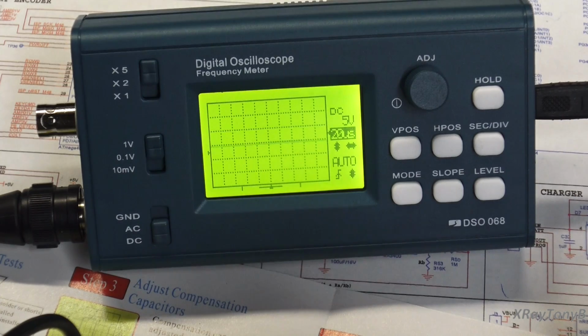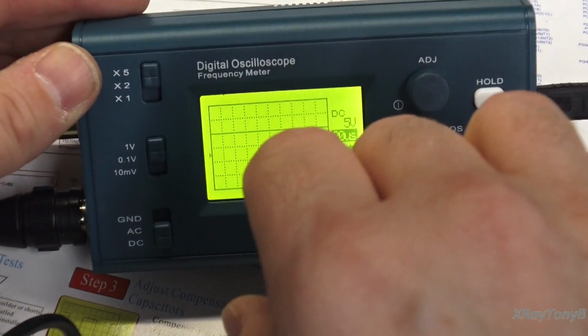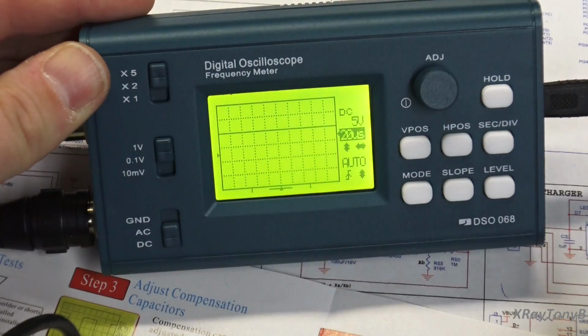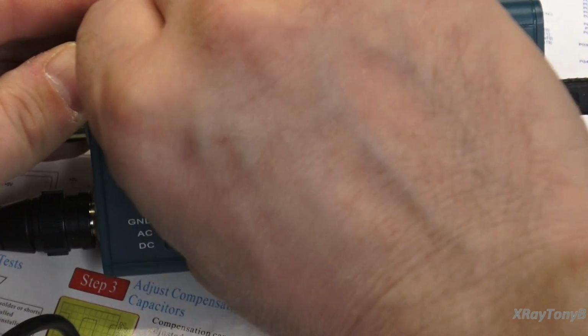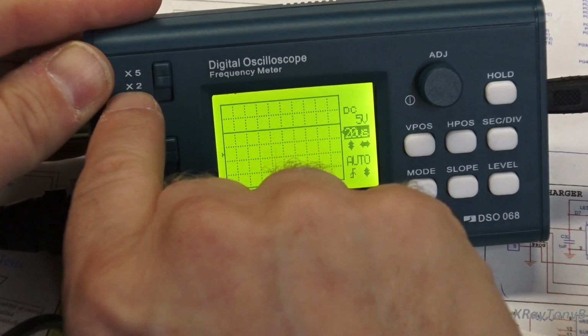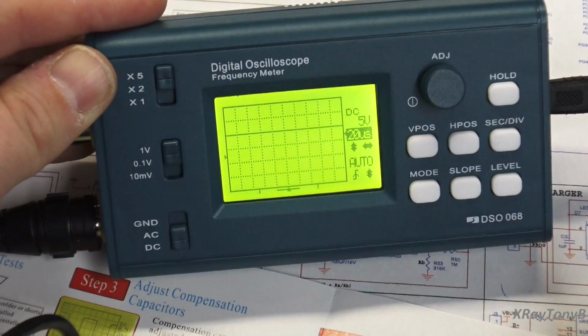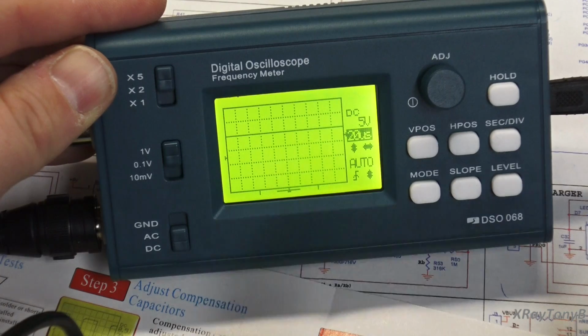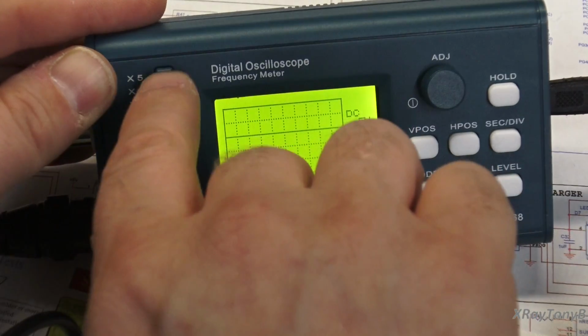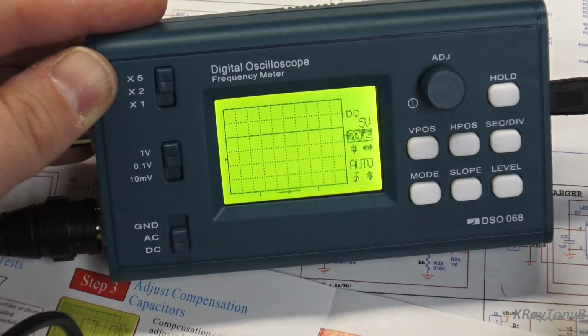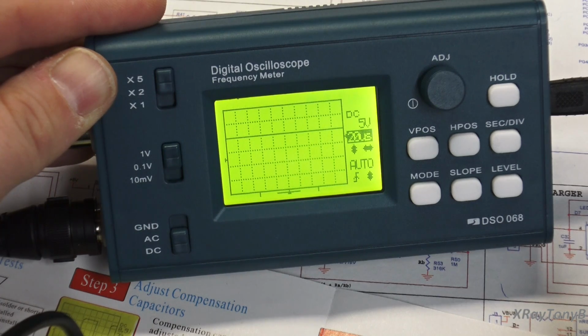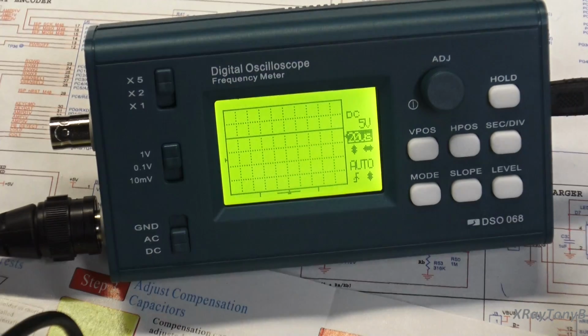If I disconnect it. Now the one thing I will tell you is the way this kit fits together, these switches are finicky and you have to make sure you positively click them into position. You can get it clicked halfway between 2 clicks and it will short both of these poles together at the same time and mess up your scaling. So if you have a problem with this being accurate, make sure that the switch is positively switched in. All right, now let's look at some waveforms.